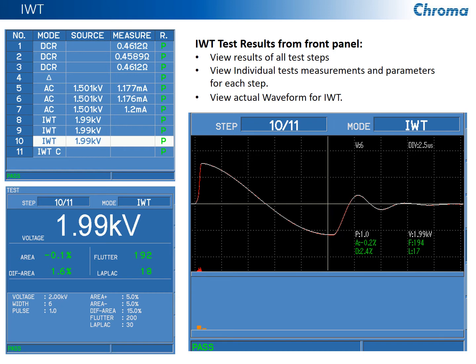Here it shows you an impulse winding test, shows you the measured voltage, shows you the results of the 4 different types of test judgments, and also gives you the actual parameters for the test below, and then of course we'll give you a pass-fail indication. The one I like, of course, is this waveform that we can also display as the test results. The red waveform is going to be the actual unit under test, where the white waveform is the known good sample that it's being compared to.